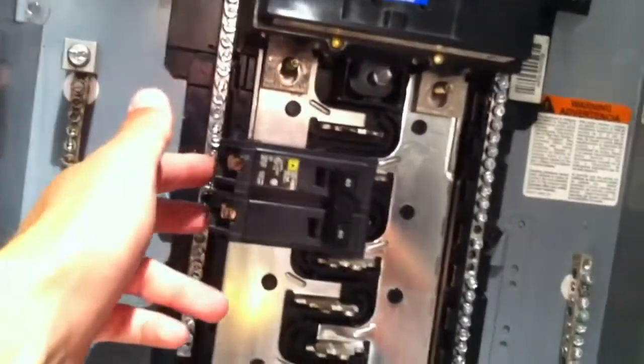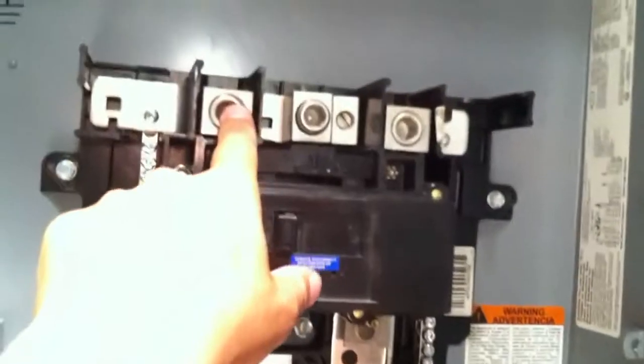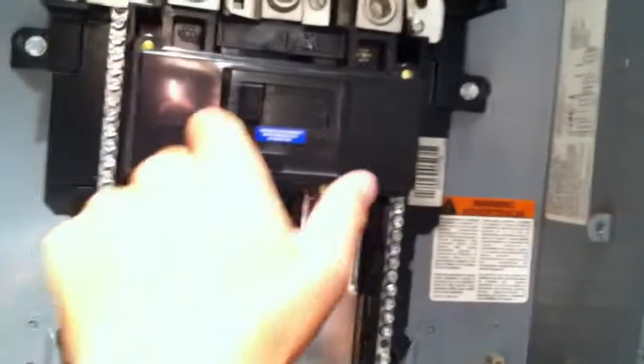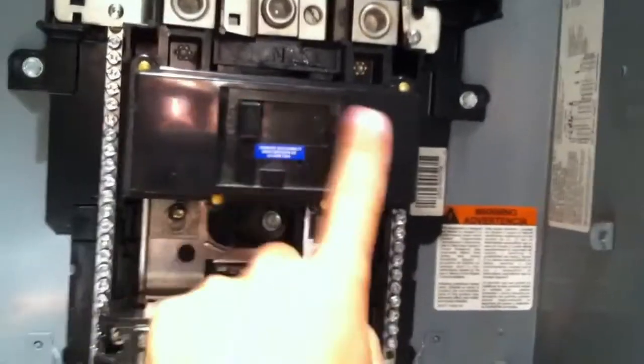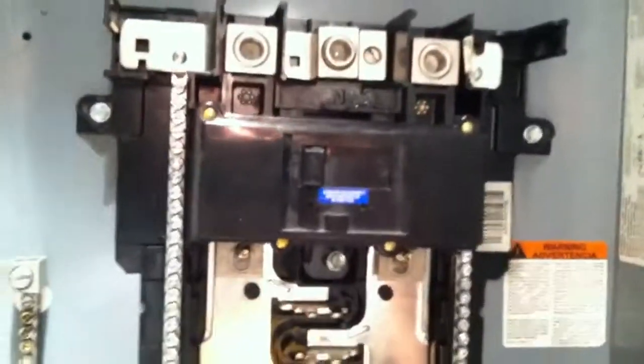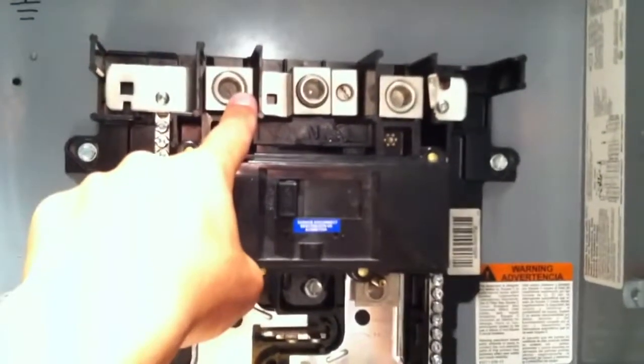But one thing I want to make clear, no matter what kind of setup you have, whether it's a main breaker like this or like this, these are both very common, larger homes have this, smaller homes have this. This feed will never shut off, no matter what. Whether this breaker is on or off, no matter which way it's flipped, or if it's tripped, it doesn't matter what's going on, these are always going to be live.